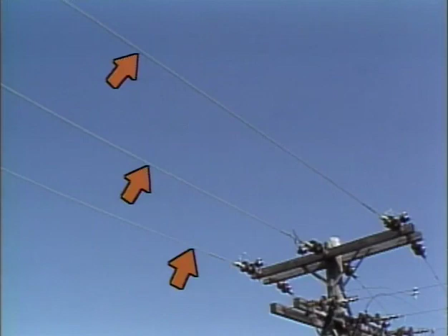There are two other conditions that can create electrical charges in previously de-energized lines. These situations involve electric field coupling and magnetic field coupling. Electric field coupling is the transfer of electricity from an energized conductor to a de-energized conductor through a medium such as air. This can occur when a line carrying a high level of energy is located in close proximity to a de-energized line. The air between these lines can pass a certain amount of electrical charge from this line to this line, energizing the line.